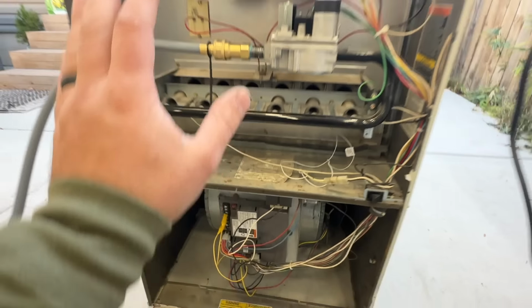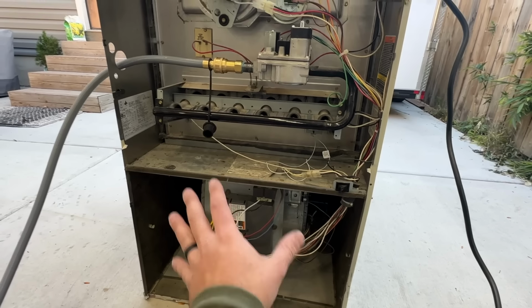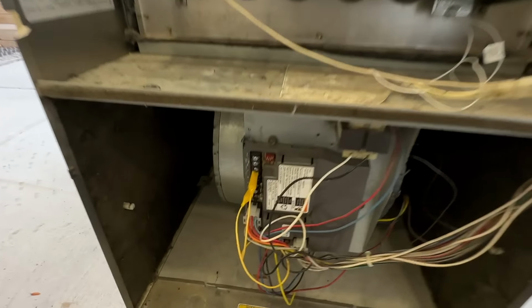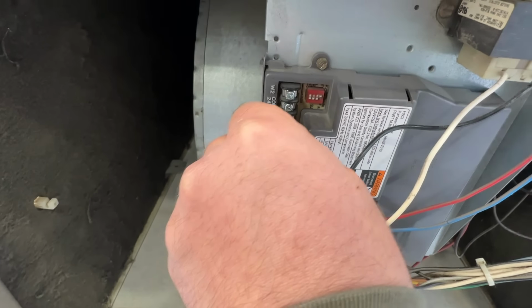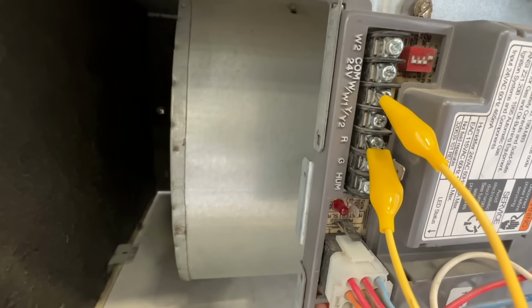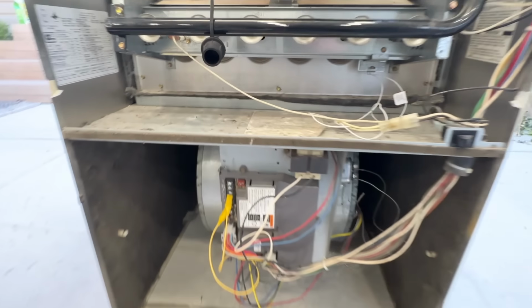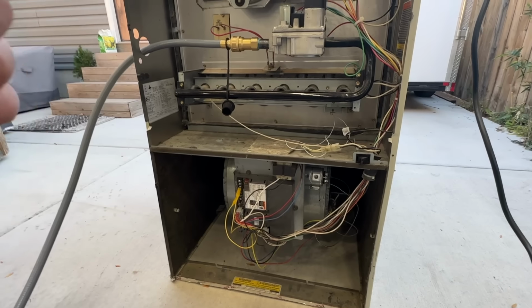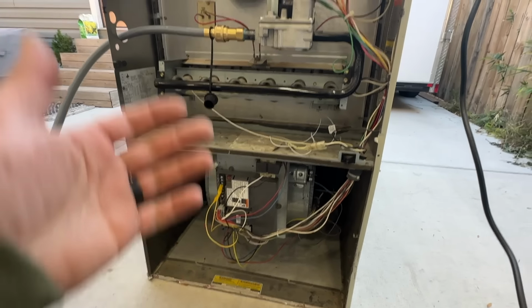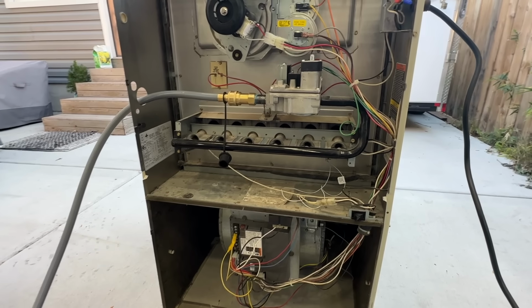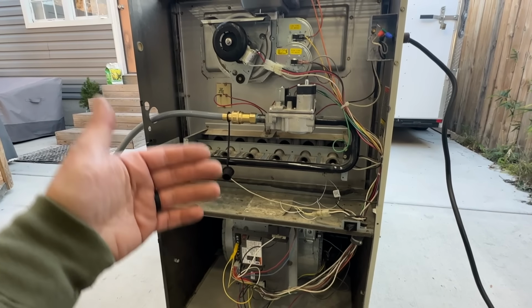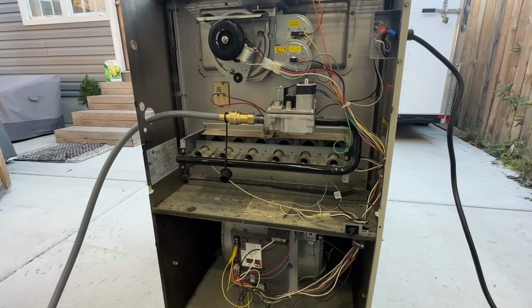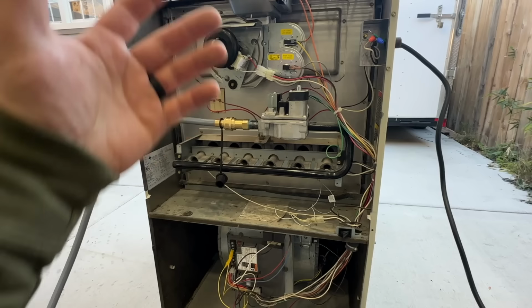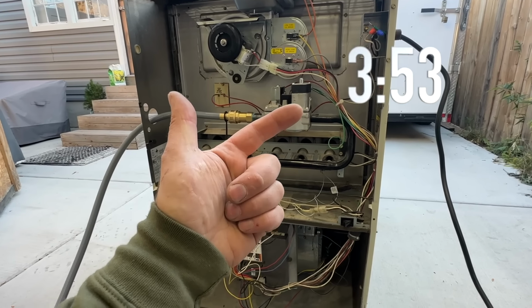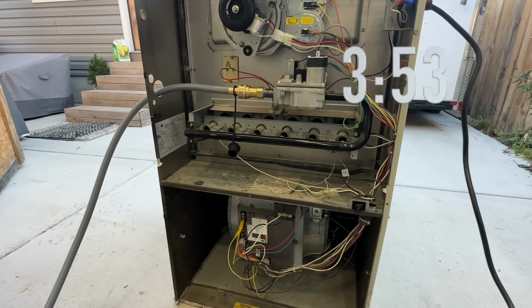So basically we just took the front covers off. We had a cover for the blower and a cover for the burner box here. And all we've done is we've jumped W and R. Now, if you don't want to jump this, all you have to do is go up to your thermostat, put it in heating mode, and you can check all of this just like we're checking. But I'm just going to run you through how a sequence of a gas furnace works, just for those of you that don't know. If you do already know how a gas furnace works, skip to this timestamp and we'll show you how to do this actual test.